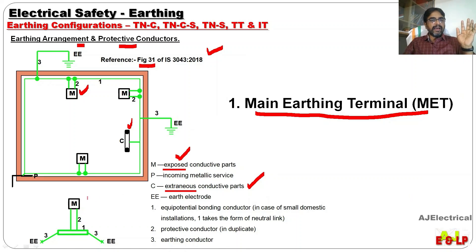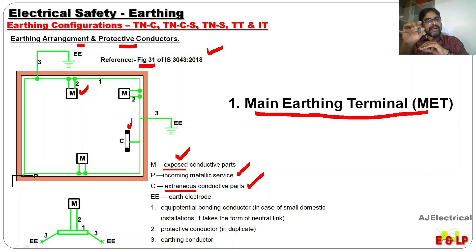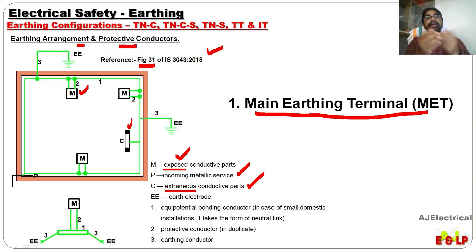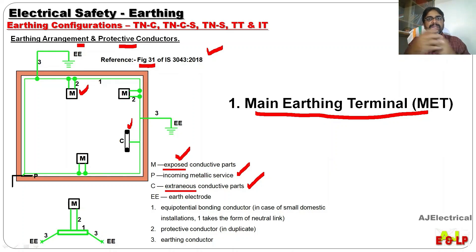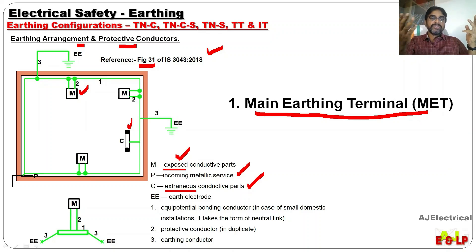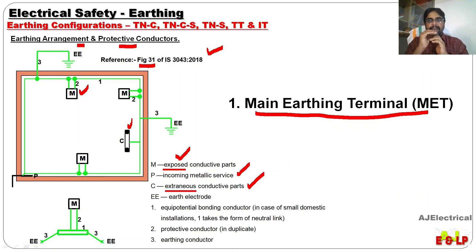If such a metal piece is near our wiring, it is better to connect it into the earthing system, as shown here. Then P is the incoming metallic service — for example, a gas service pipe — and that metal pipe also should be connected to this system. So we are doing the process of equipotential bonding, interconnecting the earthing conductors and protective conductors using the Main Earthing Terminal. MET is just like a bus — it is a common point interconnecting all the earth components. That is the duty of the Main Earthing Terminal.